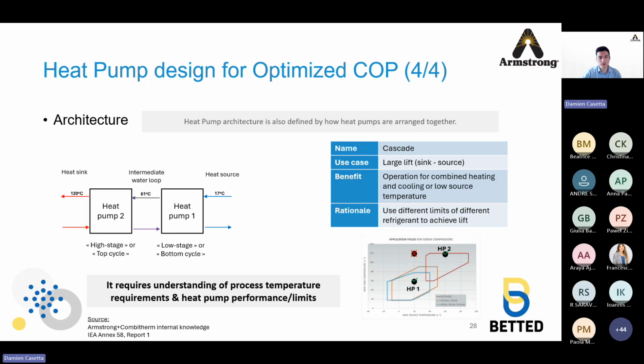But by combining different heat pumps, in this example, one is going from 17 to 61, and the other one is going from 61 to 120, then you can achieve that large lift by using different refrigerants, different technology, then optimizing each one to get the best COP in the end. Again, that requires understanding the process temperature requirements and also the heat pump performance and temperature limits. So both product heat pump and process knowledge are needed to make this happen.